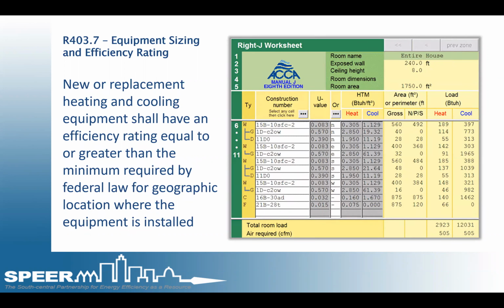Manual J is used to calculate heating and cooling loads inside the house, meaning the software uses all the available data, such as wall and ceiling insulation, window U-value, SHGC, orientation, climate zone, design parameters, infiltration, and exfiltration to calculate how much in BTUs it will take to condition the home in both heating and cooling. That BTU information is then fed into Manual S. Manual S is used to size the correct equipment, where the output matches or exceeds the BTU loads that were previously calculated.